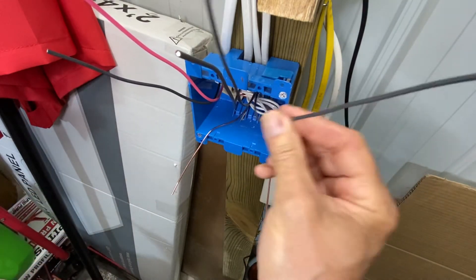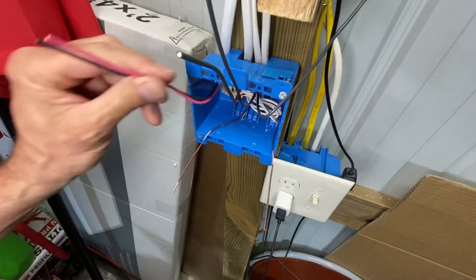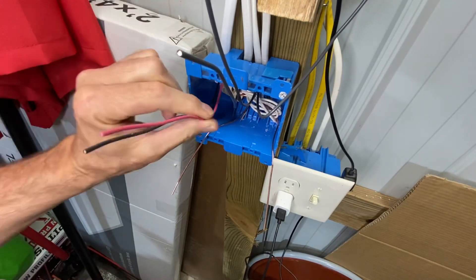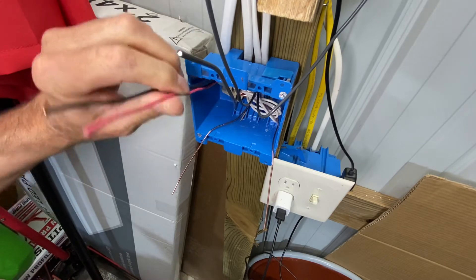Now, this is the one that goes to the light. Fold it up here. These are the two that go to the three-way. They're called travelers. Those are the two that go on the gold screws or the silver screws. Fold them up.